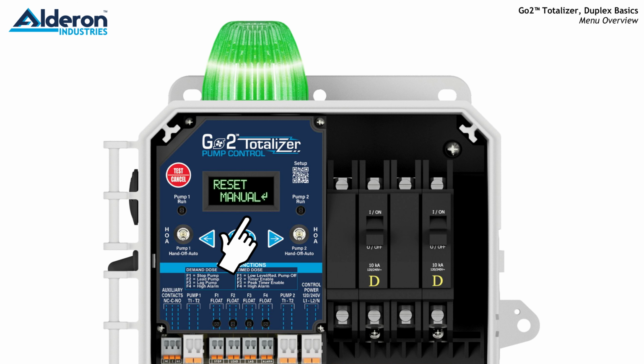Select Silence Time if you want to adjust the time the buzzer will reactivate when silenced and the system is still in alarm. For example, if the high-level alarm float activates the beacon and buzzer, and the buzzer will activate. If the buzzer is silenced by an operator and the high-level float is still activated for more than 24 hours, which is factory default, then the buzzer will be reactivated to alert that a high-level alarm is still occurring.